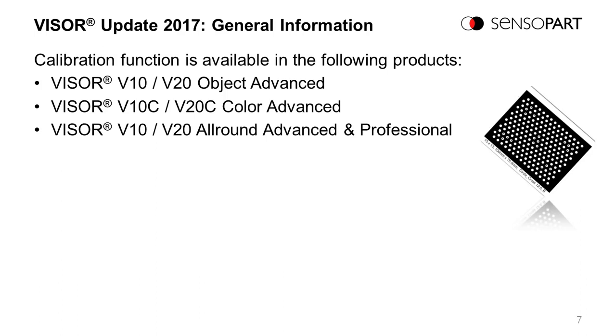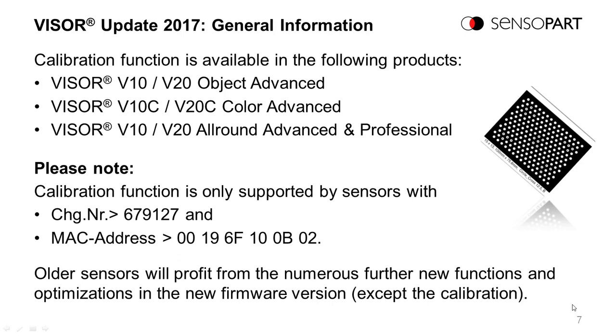Calibrations available in these visors. The ones that have a caliper detector also have calibration. Except for visors over about a year or two old, something with the math coprocessor, we can't do calibration on those, but you can still update to the latest firmware and take advantage of all the other new features.